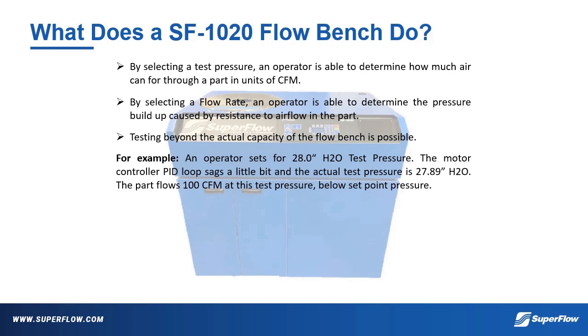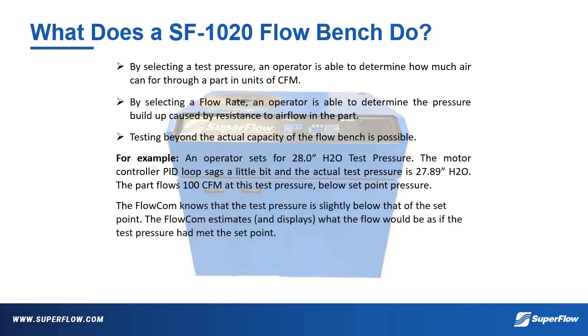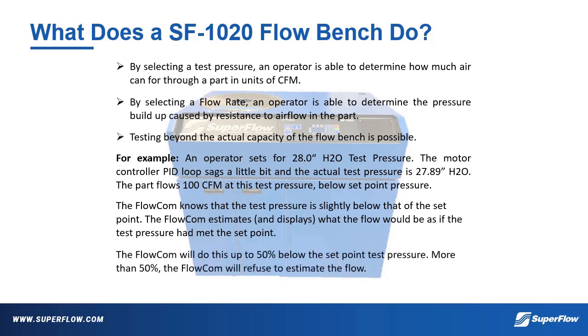For example, an operator sets for 28 inches of water test pressure. The motor controller PID loop sags a little bit, and the actual test pressure is 27.89 inches of water. The part flows 100 CFM at this test pressure, which is below the set point pressure. The FlowCom knows that the test pressure is slightly below that of the set point. The FlowCom estimates what the flow would be as if the test pressure had met the set point. The FlowCom will do this up to 50% below the set point test pressure. More than 50%, the FlowCom will refuse to estimate the flow.